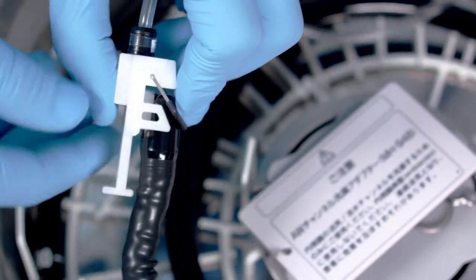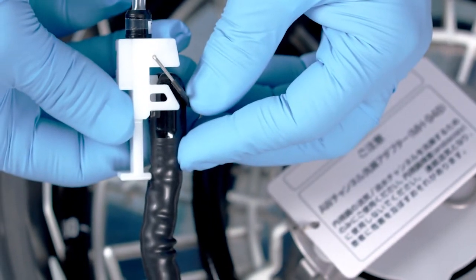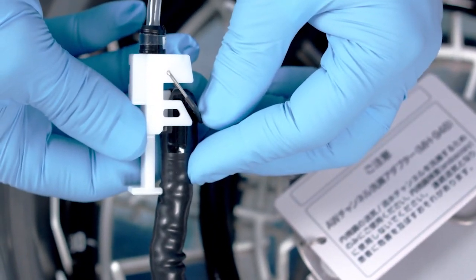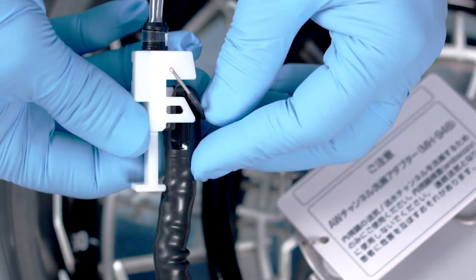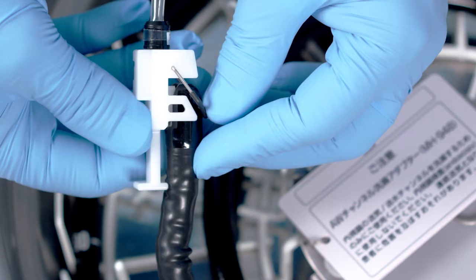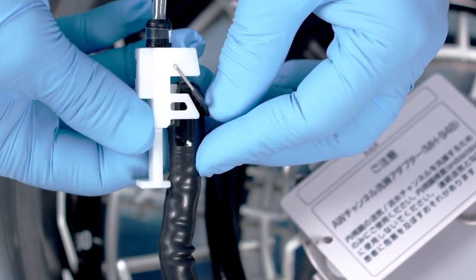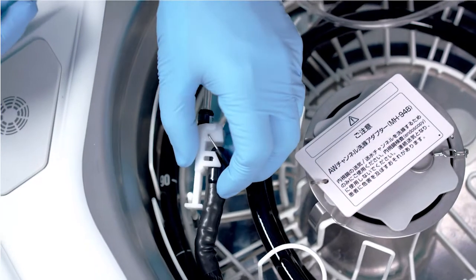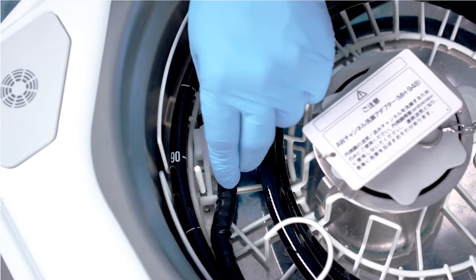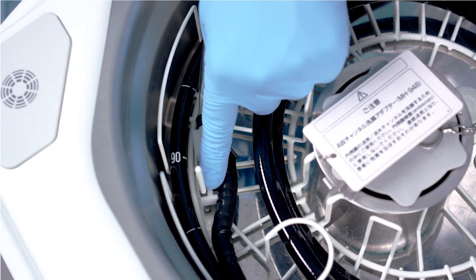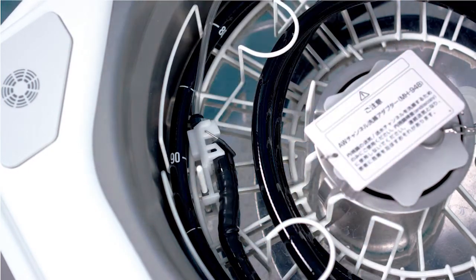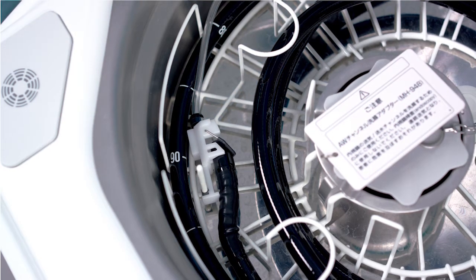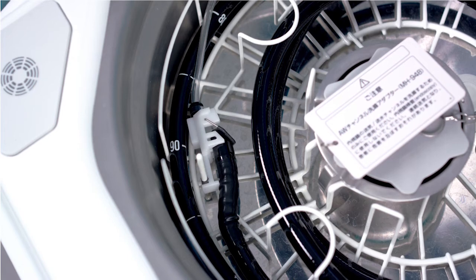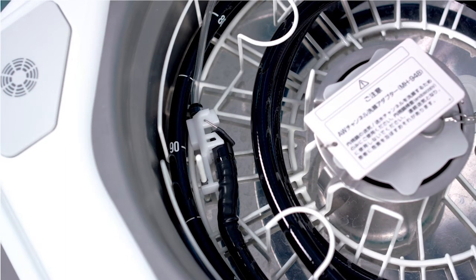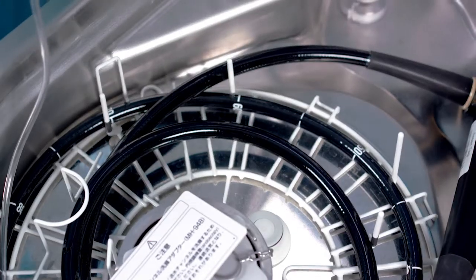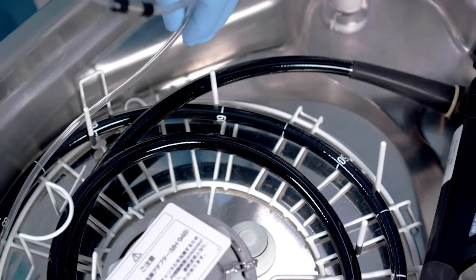Next, confirm that the nozzle of the endoscope side connector is contacting the instrument channel outlet. If there is a clear gap between the nozzle and the instrument channel outlet, remove the connecting tube and retry. Otherwise, reprocessing of the forceps elevator may be insufficient. Then, set the distal end of the insertion tube in the reprocessing basin while the groove of the endoscope side connector is attached to the pin on the proximal side of the retaining rack of the reprocessing basin. The connector must be in contact with the pin on the retaining rack. Now, wrap the connecting tube outside of the pins of the retaining rack.